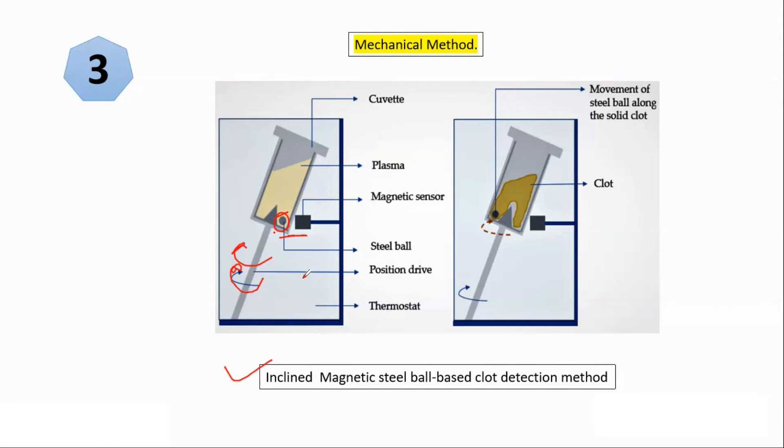So everything is going to rotate as whole system is rotating, but due to presence of magnetic sensor, steel ball will stay at that position. As plasma is liquid in nature at this point of time, so it will not take away the steel ball away from the magnet. But as soon as clot gets formed, or clot gets formed, so clot is solid. So here when the instrument is gonna rotate, the clot will rotate as plasma is coagulated so it is solid.